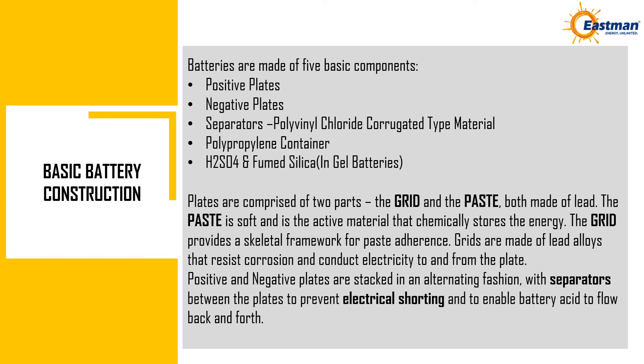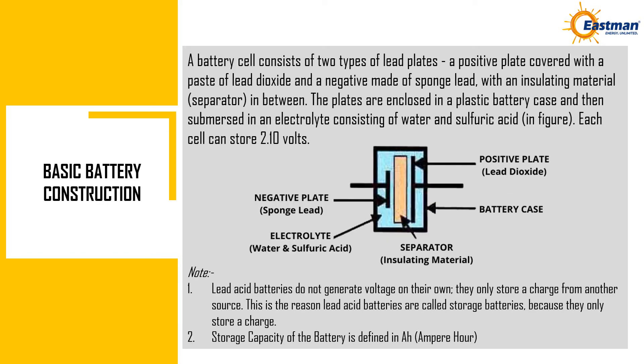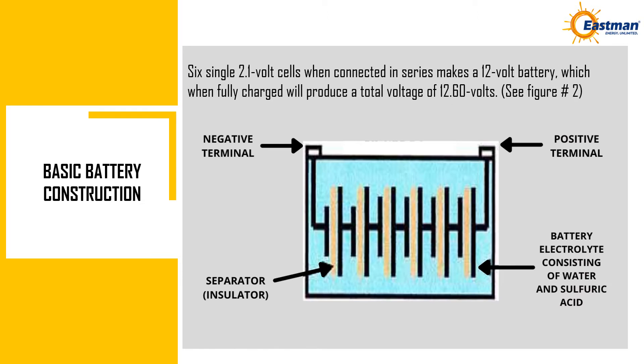Positive and negative plates are stacked in an alternating fashion, with separators between the plates to prevent electrical shorting and to enable battery acid to flow back and forth. A battery cell consists of a positive plate covered with a paste of lead dioxide and a negative plate made of sponge lead, with an insulating separator in between. The plates are enclosed in a plastic battery case and submersed in an electrolyte of water and sulfuric acid. Each cell can store 2.10 volts. Lead acid batteries do not generate voltage on their own — they only store a charge from another source, which is why they are called storage batteries. Six single 2.1 volt cells connected in series make a 12 volt battery, which when fully charged produces a total voltage of 12.60 volts.